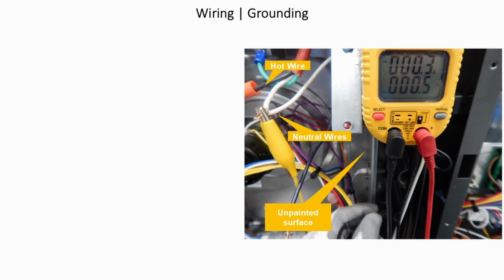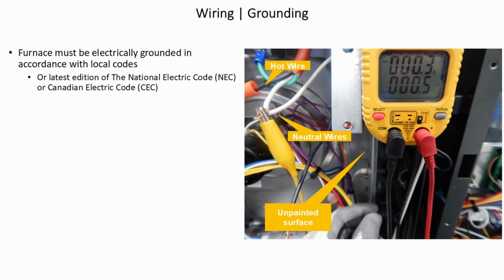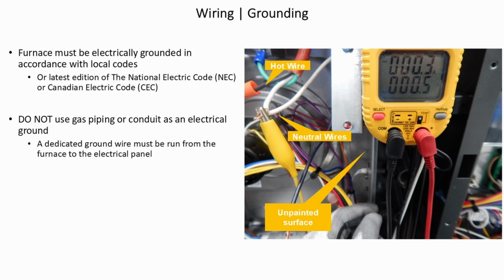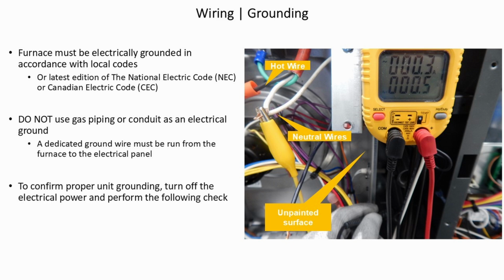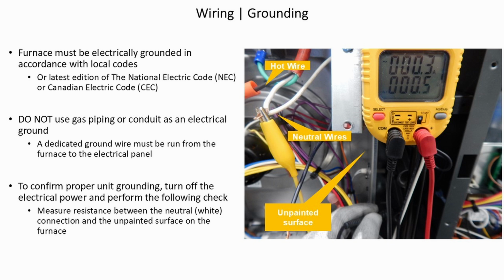Wiring, grounding. Furnace must be electrically grounded in accordance with local codes, or the latest edition of the National Electrical Code, NEC. Do not use gas piping or conduit as an electrical ground. A dedicated ground wire must be run from the furnace to the electrical panel. To confirm proper grounding, turn off the electrical power and perform the following check. Measure resistance between the neutral, white wire, and the unpainted surface of the furnace. Resistance should be 10 ohms or less.